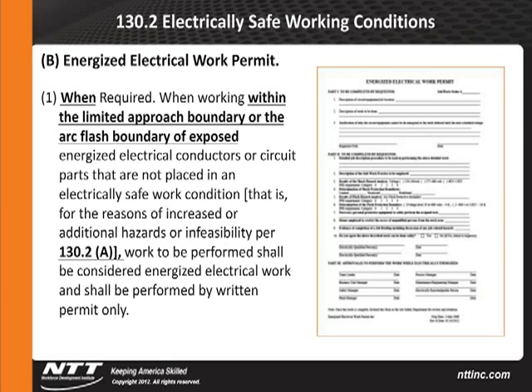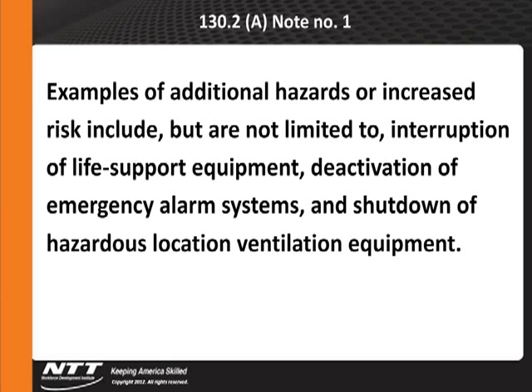So what are examples of additional hazards or increased risk? According to NFPA 70E, here's a note: examples of additional hazards or increased risk include, but are not limited to, interruption of life support equipment, deactivation of emergency alarm systems, and shutdown of hazardous location ventilation equipment. There's a caveat that goes along with it, used in the industry, where human life is on the line. So interruption of life support: hospitals, nursing homes, assisted living facilities; deactivation of emergency alarm systems. What if you have monitoring for an ammonia refrigeration system? You're protecting your employees and the public. What if you have welding fumes and so forth? Under those circumstances, if I shut it off and put human life on the line, I would be allowed to do some of this work in an energized state using a work permit.